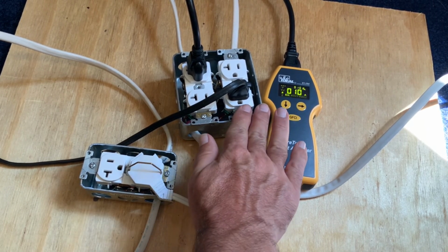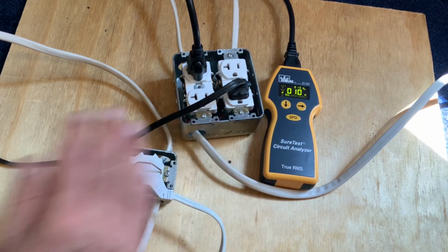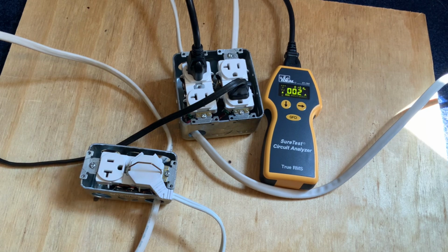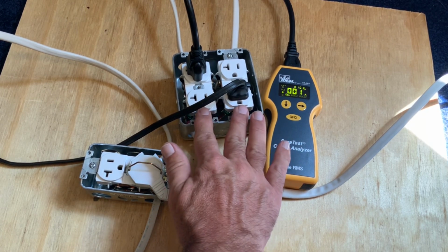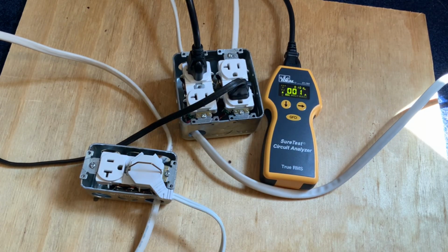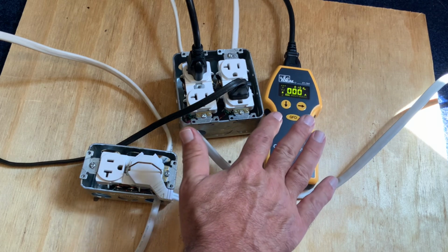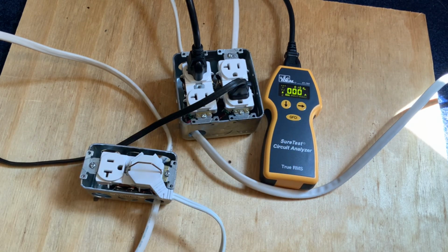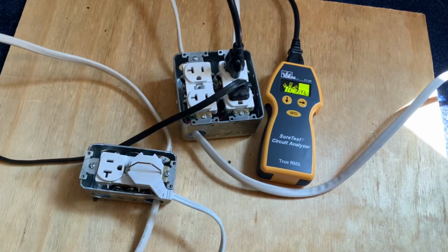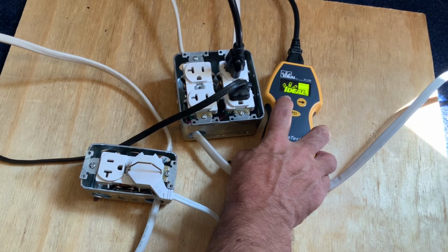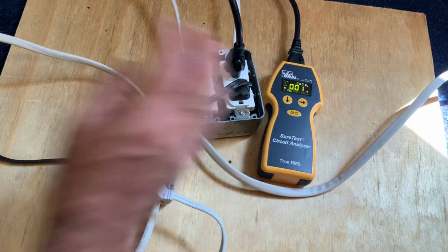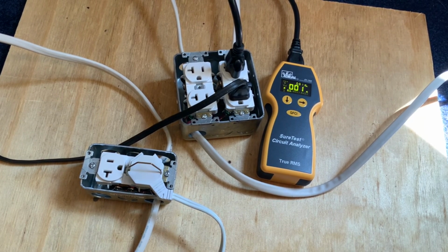But now here's my other hot that's sharing the neutral. If I turn this heater on and draw 11 amps out of the other hot, because of the shared neutrals, this is showing me only 1 amp of current being drawn now, because this is basing the load on the neutrals, not on the hots. So because of the shared neutral, I'm not getting an accurate representation of how much current is being loaded down on each of these breakers. Right now I'm pulling 10 to 11 amps out of each breaker, and I'm looking at either hot here, either outlet goes back to those hots. And again, 0 to 1 amp is all that's showing up there. But if I turn off one of these heaters, that will jump right up to the 10 amp load.